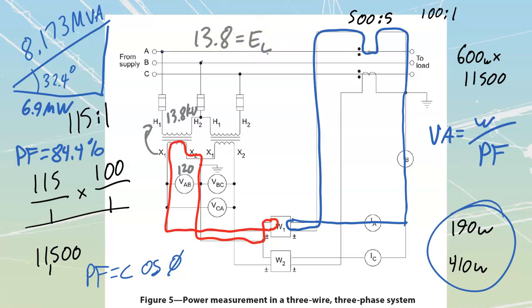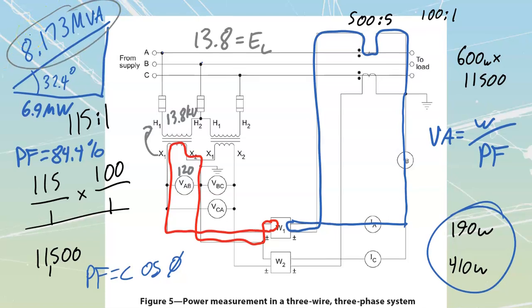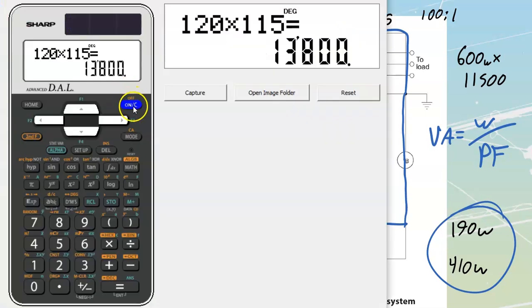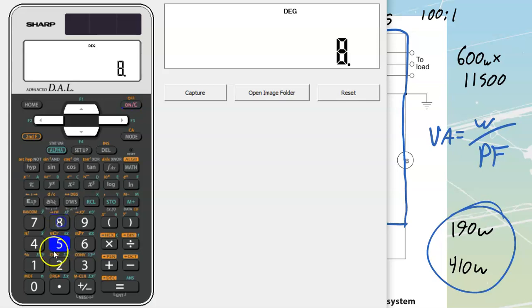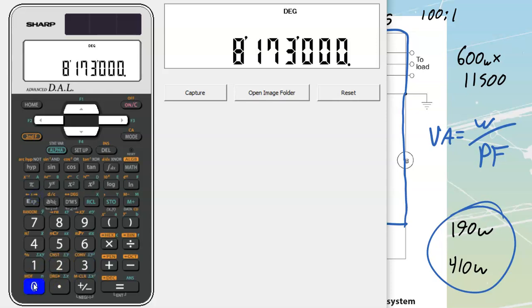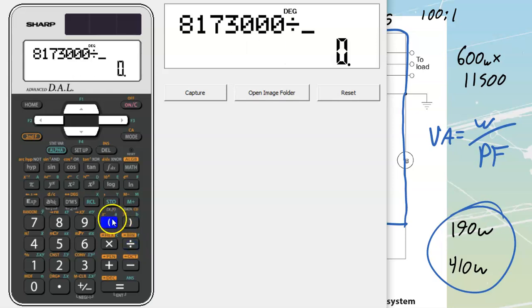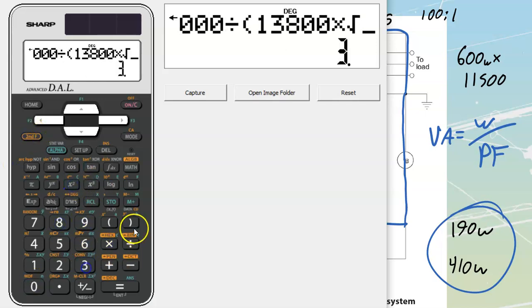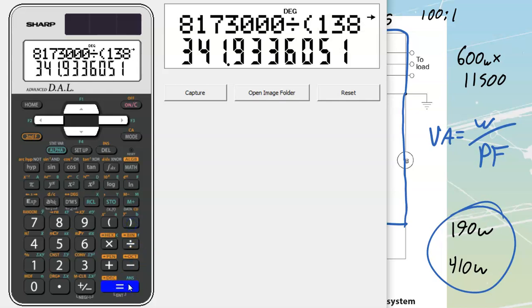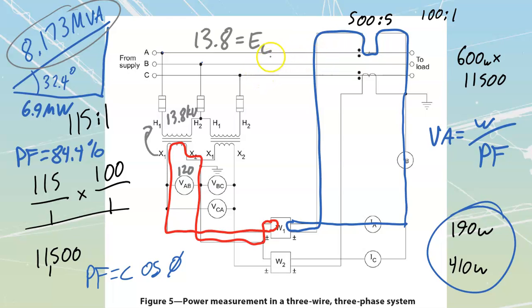Okay, 13.8. Now that we've got our E line and we have our total amount of VA, this 8.173 mega VA, we can use our VA formula to find our total amount of line current. I line is equal to my VA divided by my E line times root 3. So 8,173,000 divided by my value of voltage, 13,800, times root 3, which gets me out to a value of 341.9 amps. That's going to be my I line, 341.9. So we'll call that 342 amps line.